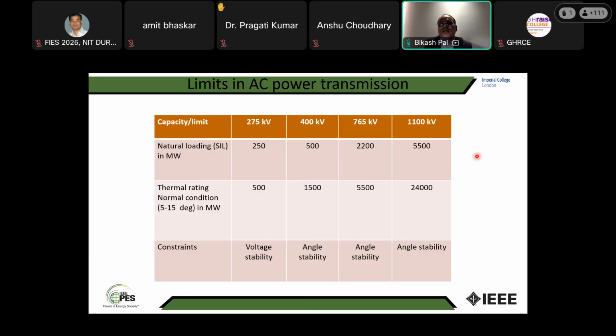It's a hotel in Beijing. It's a good internet. So 1100 kV, typically in a large country like say China, where I am now today. So they have this natural loading. You see that surge impedance loading, which is 5,500 megawatt. Now let's talk a little bit about the surge impedance loading concept. So what is a surge impedance loading or natural loading?